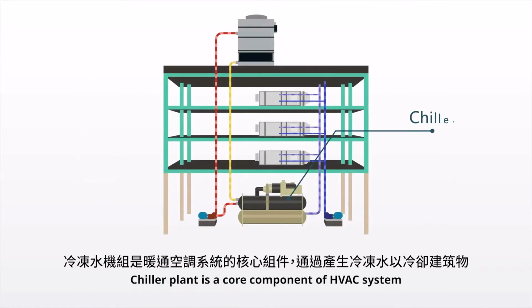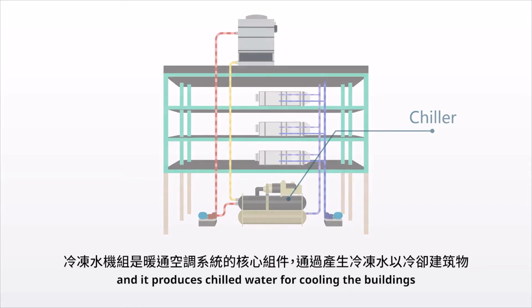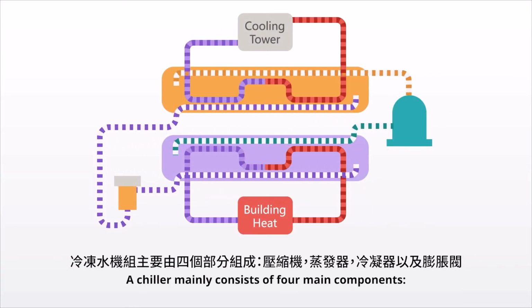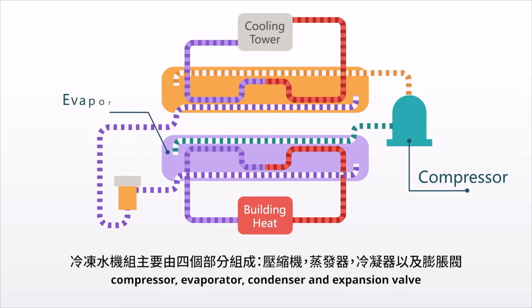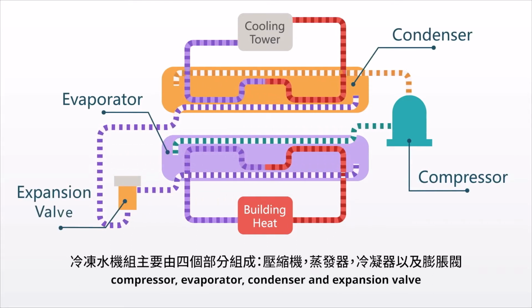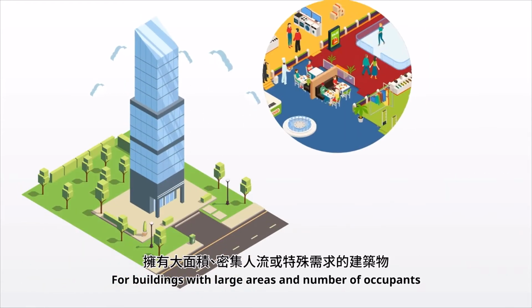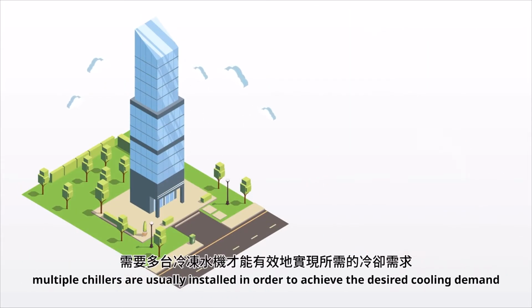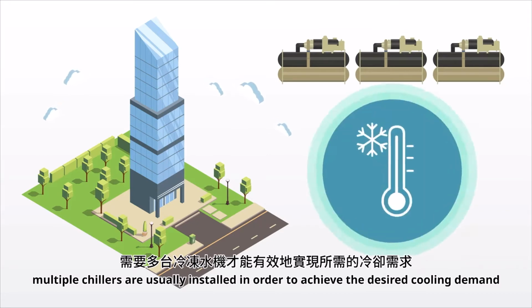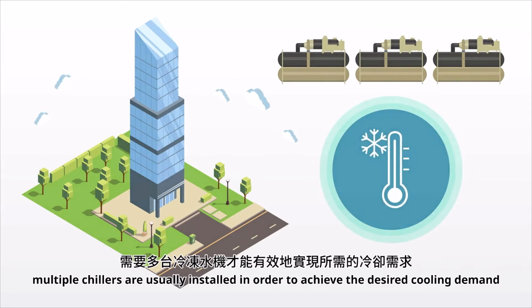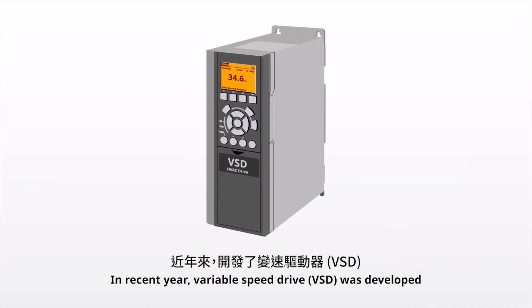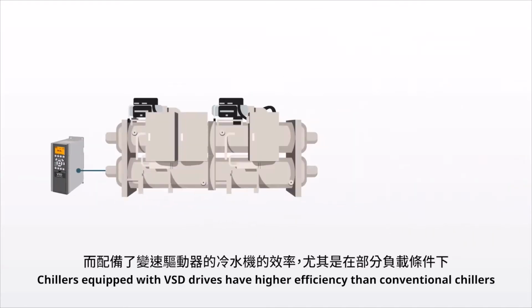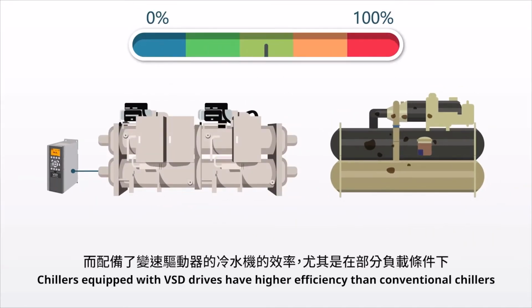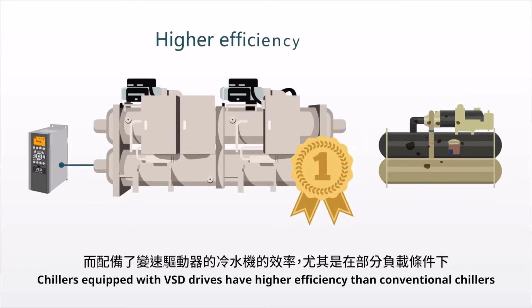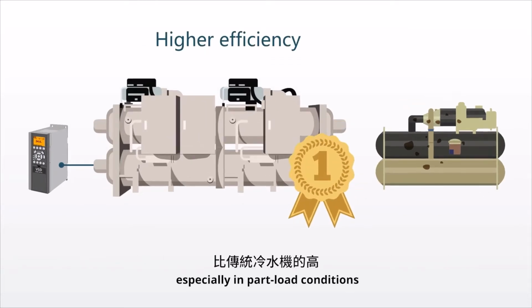Chiller plant is a core component of HVAC systems, and it produces chilled water for cooling the buildings. A chiller mainly consists of four main components: compressor, evaporator, condenser, and expansion valve. For buildings with large areas and number of occupants, multiple chillers are usually installed in order to achieve the desired cooling demand. In recent years, variable speed drive (VSD) was developed. Chillers equipped with VSD drives have higher efficiency than conventional chillers, especially in part load conditions.